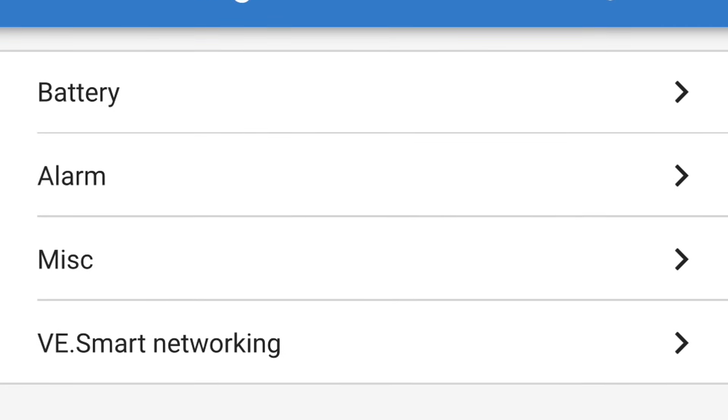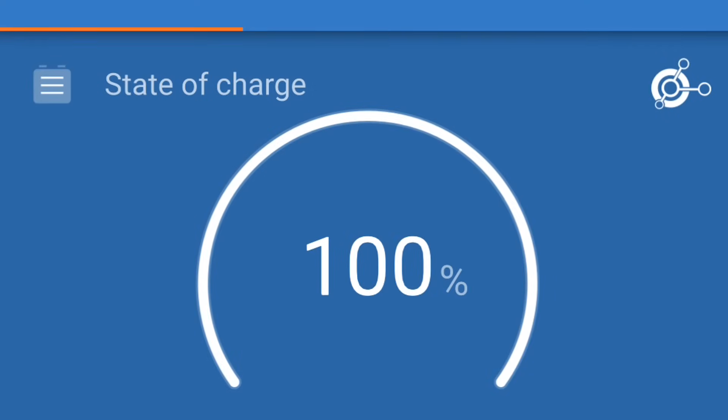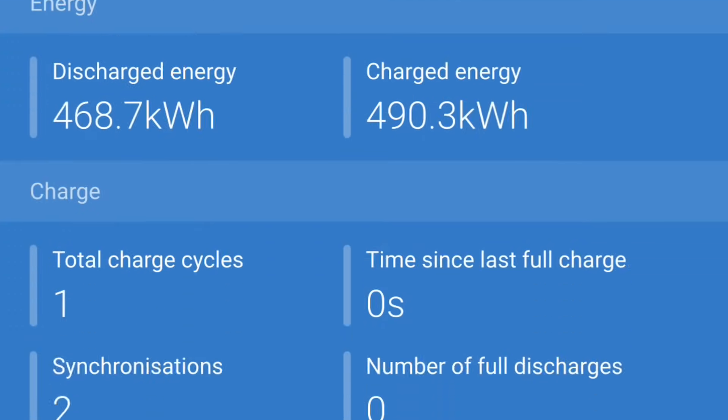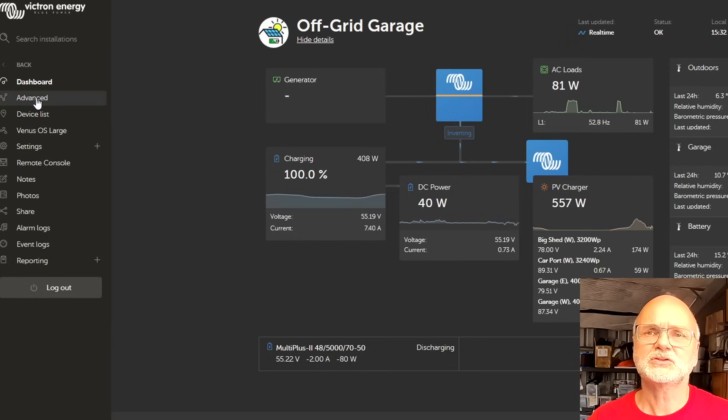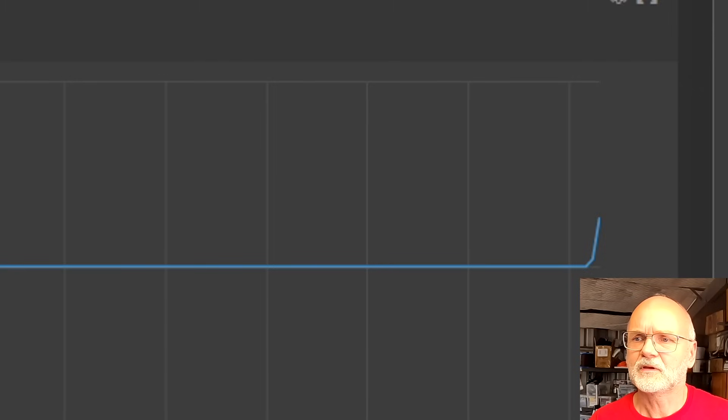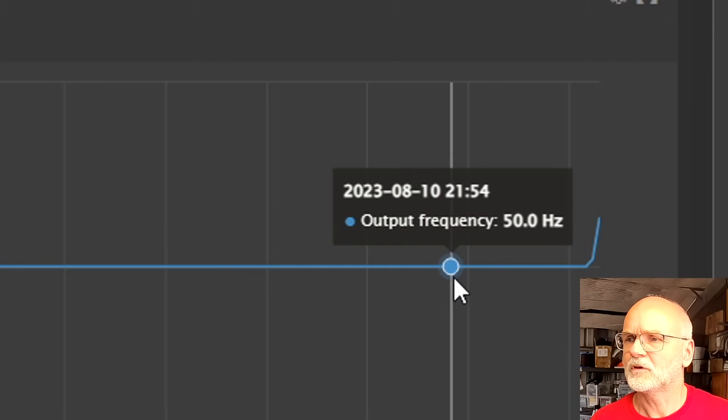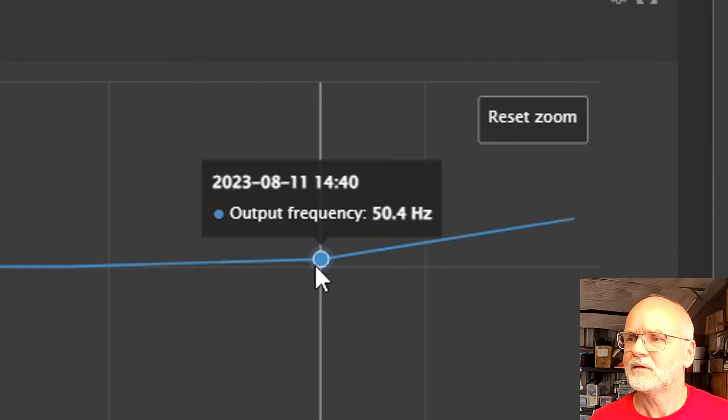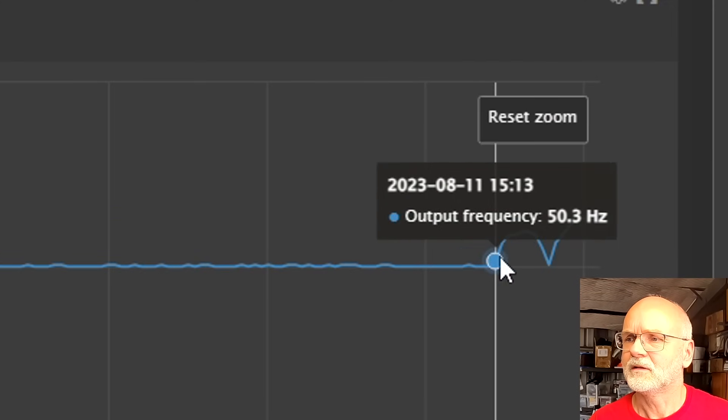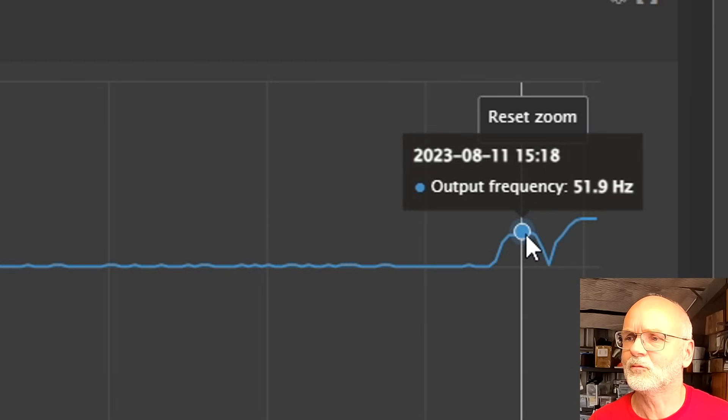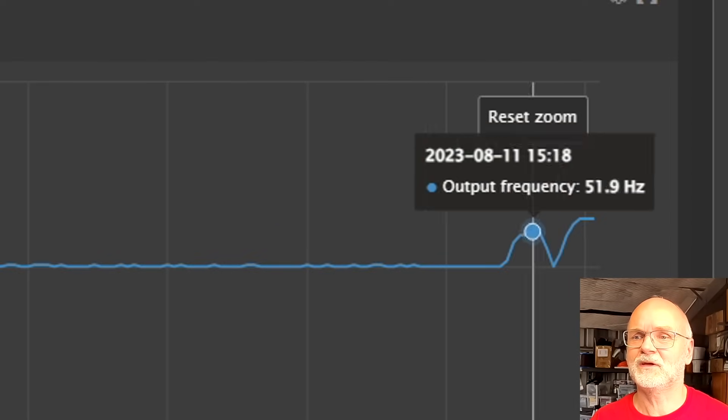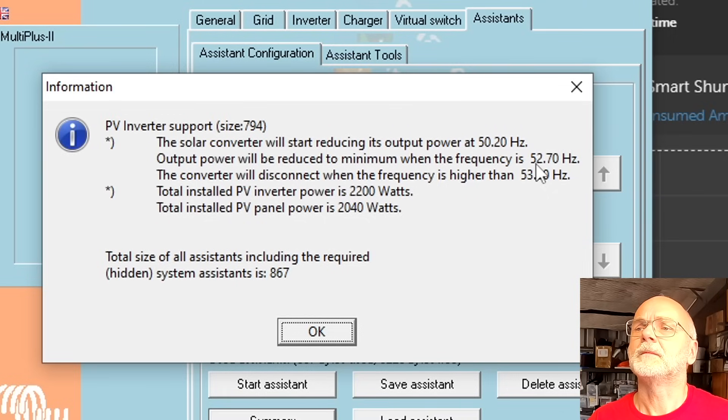Our smart shunt has just reset to 100%. You can see time since last full charge zero seconds. We are at 52.6 hertz. You can have a look here in the advanced tab - frequency 50 hertz, 51, 50.1, 49.9, and then here at the end we can see it actually going up. You can see our two charge cycles we had this afternoon where the frequency actually goes up. It does exactly what we have told it in the assistant - goes up to 52.7 and at 53 there's no power output of the micro inverter.